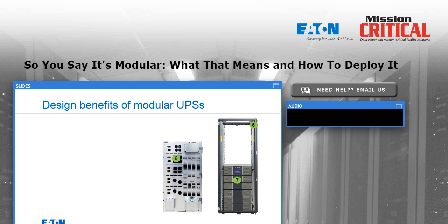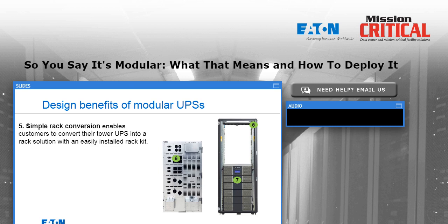This is a picture of this type of UPS system from the back, and you can see that the receptacles that I may choose for the back of this UPS system are user selectable. So at the time of the original order, I can think into the future and say, okay, I'm going to be plugging in X number of racks of servers possibly in the next 6 months or the next year. What kind of twist lock receptacle might I need? Maybe I'm looking to plug in rack power strips into these receptacles on the back of the UPS, or maybe I'm plugging in individual server chassis directly into the back of a UPS system of this size.